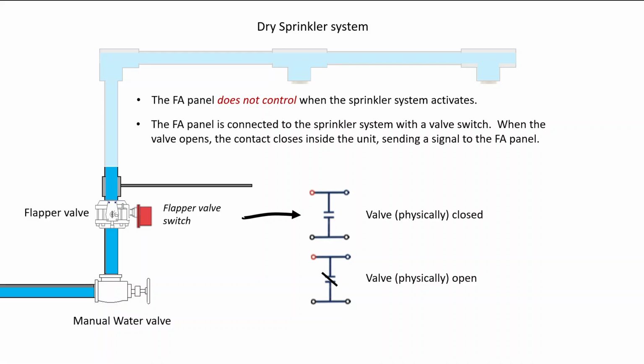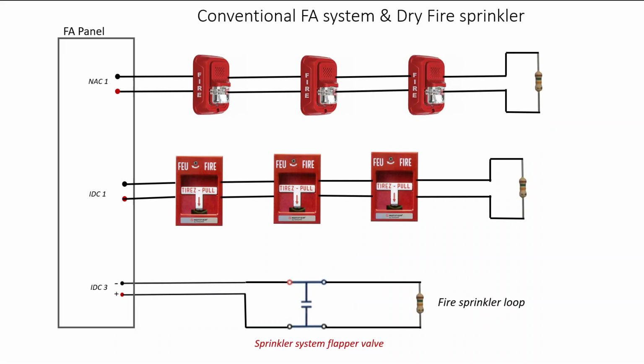Let's see how it connects into a dry conventional system. So there's our conventional Class B, and again we've got our sprinkler system flapper valve down at the very bottom there, and during normal operation those contacts should be open, and it's conventional, so there's an end-of-line resistor and current flowing through the whole thing. A little bit of current, supervisory current, same as the previous system we looked at.